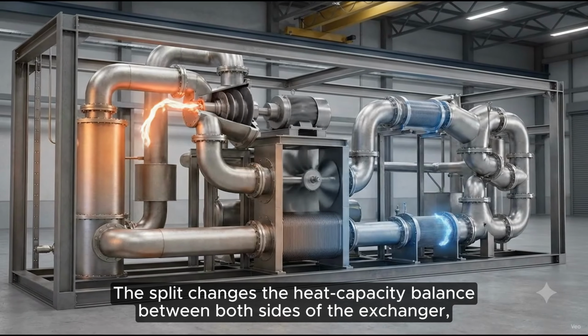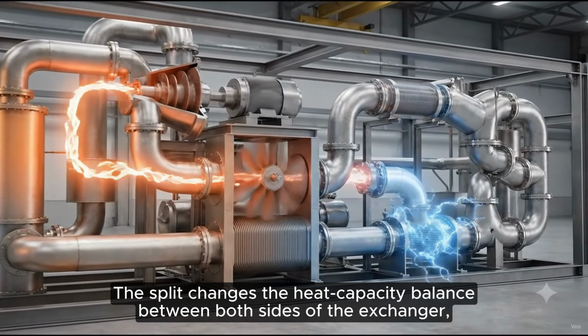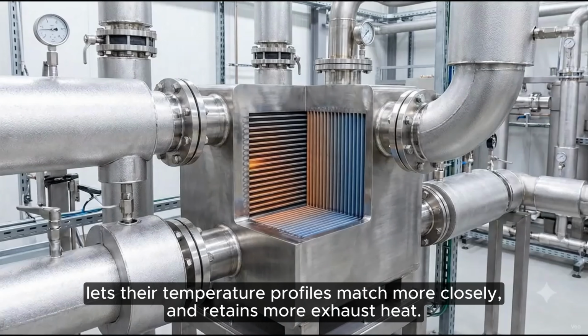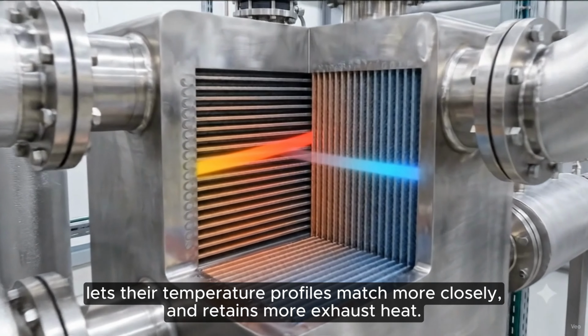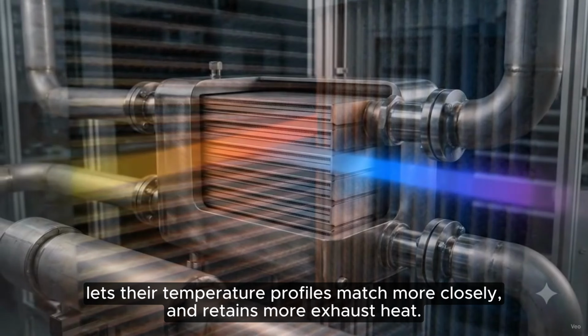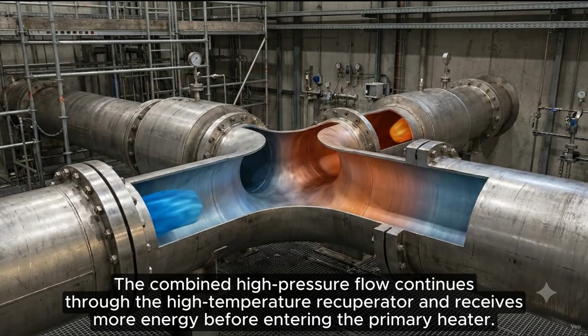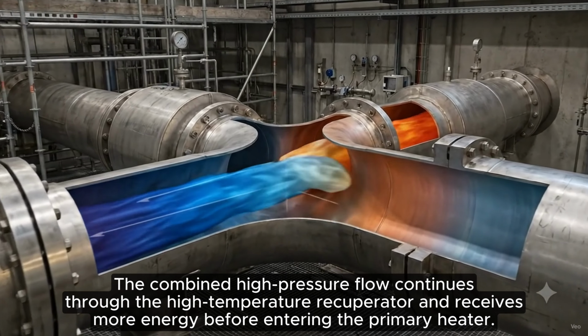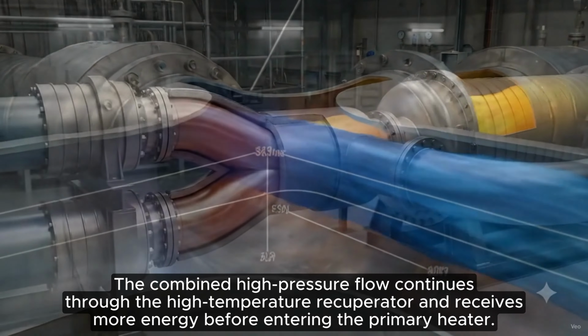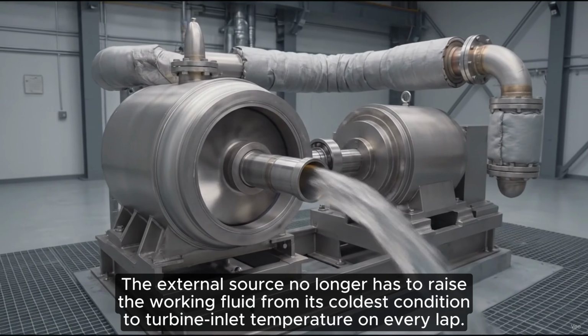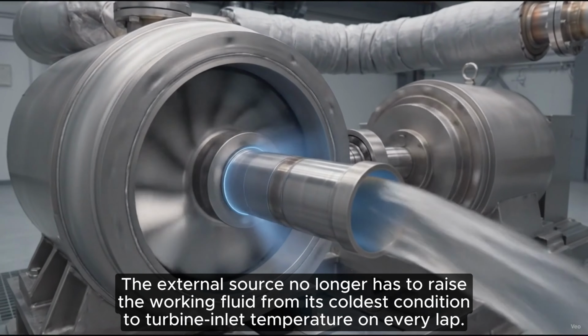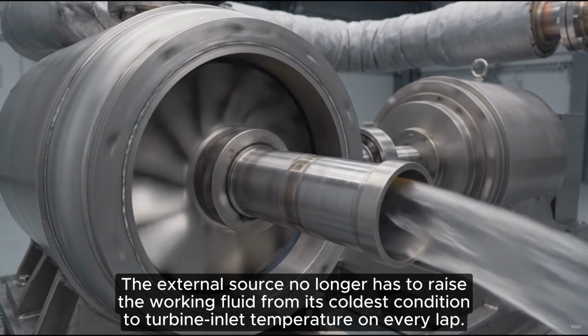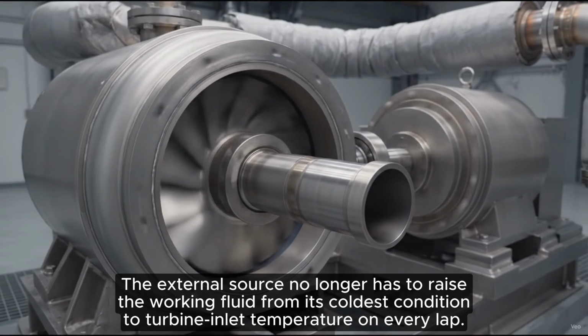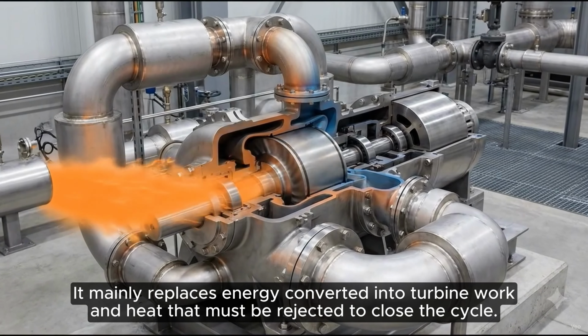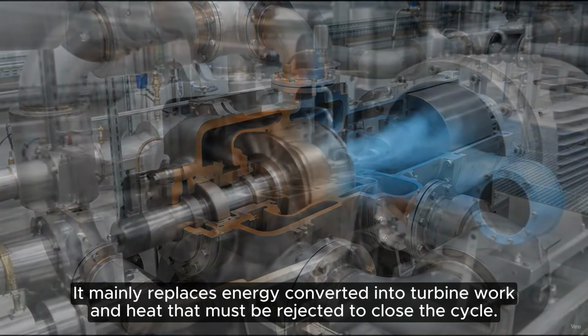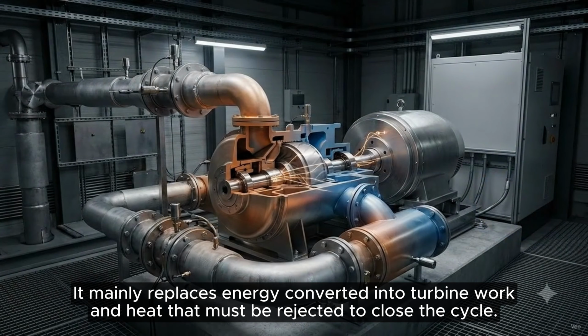The split changes the heat capacity balance between both sides of the exchanger, lets their temperature profiles match more closely, and retains more exhaust heat. The combined high-pressure flow continues through the high-temperature recuperator and receives more energy before entering the primary heater. The external source no longer has to raise the working fluid from its coldest condition to turbine inlet temperature on every lap. It mainly replaces energy converted into turbine work, and heat that must be rejected to close the cycle.